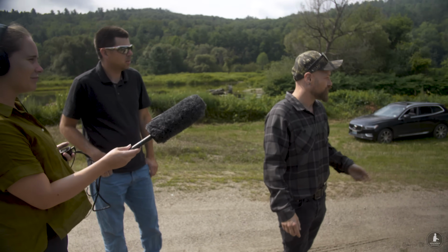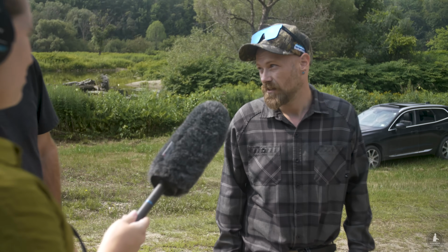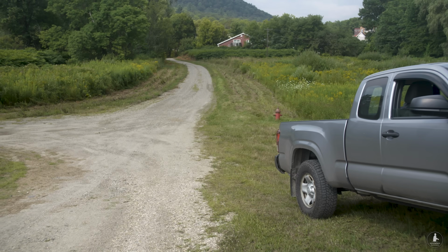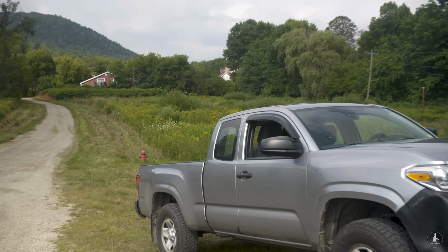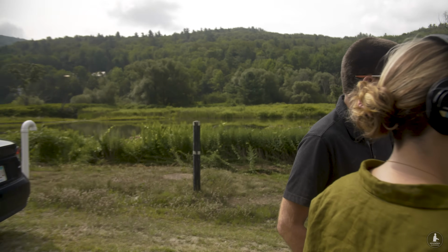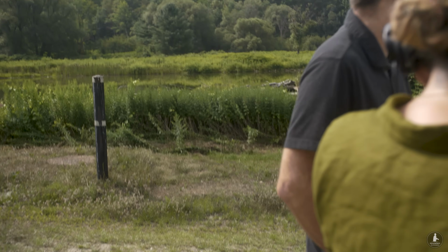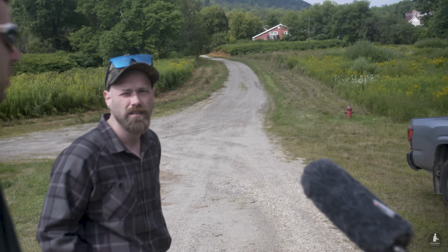That well is actually vulnerable, and you could fortify it with free rocks from the town. Anyone could drive into that snowplow, and break it. Yeah. They have access to it. So, when I was an operator, it's like rocks are free. Yeah. I don't have to buy anything, so I would just put some big boulders around it. That one too. And that's even an oops. Like if someone comes down here doing snow removal and they accidentally back into it. Physical security is just as important too. That's a really good idea.